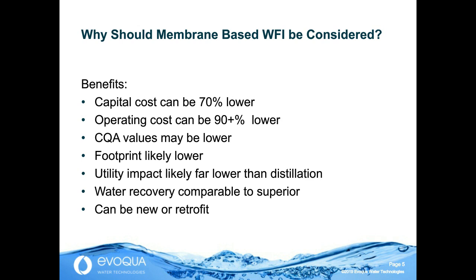So it's not just a matter of possibly saving in operating costs with lower utilities, but one should consider the impact on a steam plant, on a chiller plant, that there may be additional savings there. The overall water recovery from membrane systems can be comparable to distillation systems. Depending upon the configuration, it could be superior. And these membrane-based WFI systems can be all new, but portions can be retrofit, potentially added to take a portion of existing purified water systems and further purify that to produce water for injection. So very practical new, but also very practical in retrofit situations, for very attractive economics.